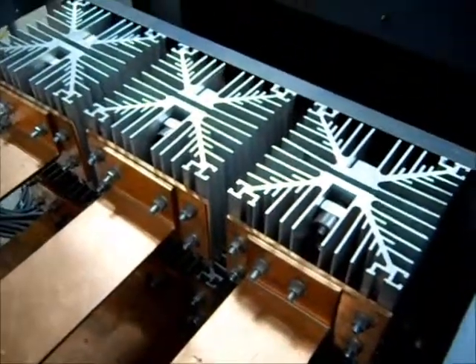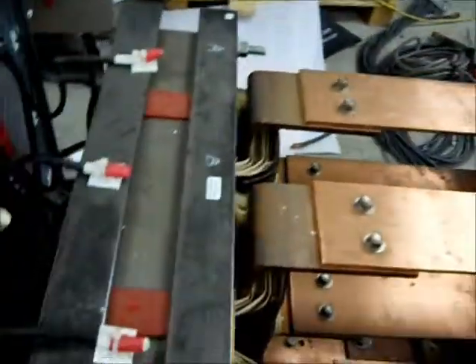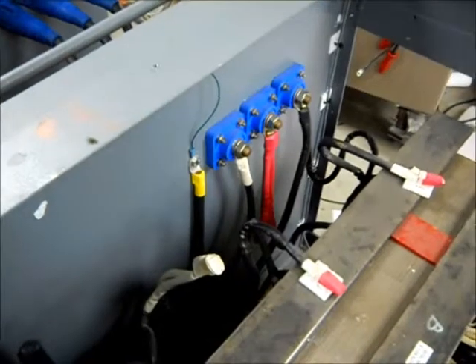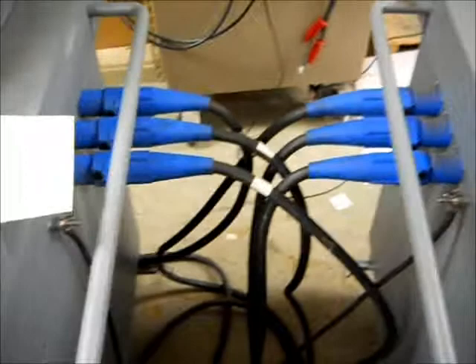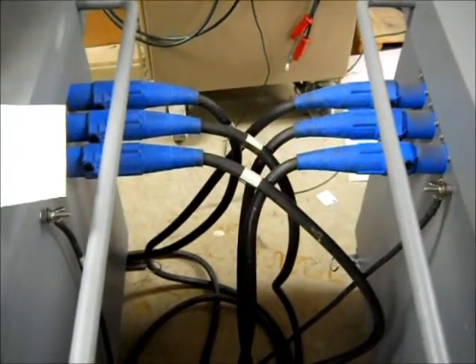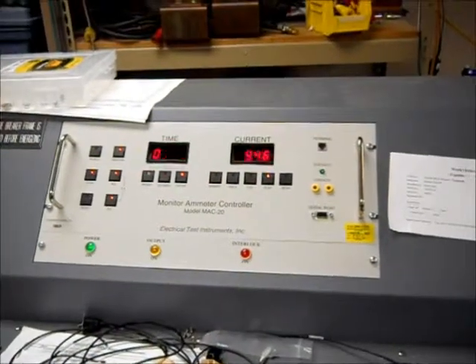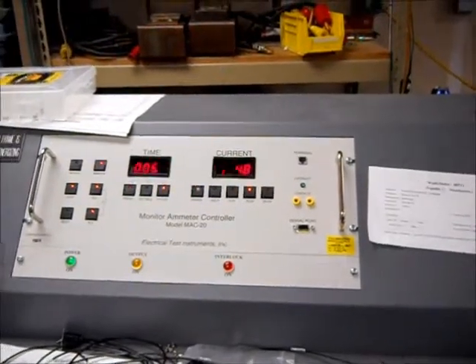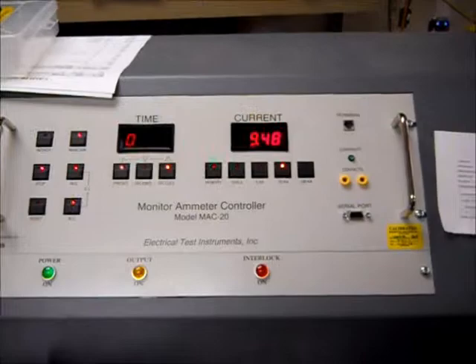Those are all solid-state diodes — these originally had selenium rectifiers. There's the three-phase transformer, the input three-phase variable, and that's the connection between the two test sets. The test set itself uses the MAC-20, which I designed — normally used for AC test sets, but also for DC test sets such as this.